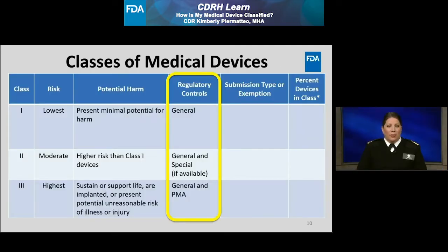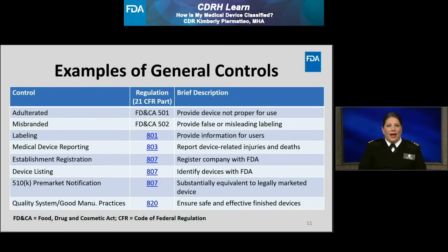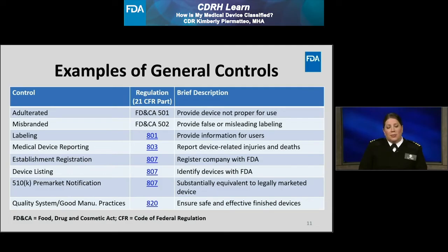Regulatory control increases from Class 1 to Class 3. Devices in all three classes are subject to general controls unless exempted by the regulations. In addition to complying with general controls, Class 2 devices may also be subject to special controls. Class 3 devices must comply with general controls as well as premarket approval controls. Examples of general controls include requirements for companies to register their establishments and list their devices with the FDA, manufacture devices in accordance with good manufacturing practices, and label their devices in accordance with FDA's labeling regulations. If a device is exempted from a specific general control, such an exemption would be stated in the classification regulation for that particular device.